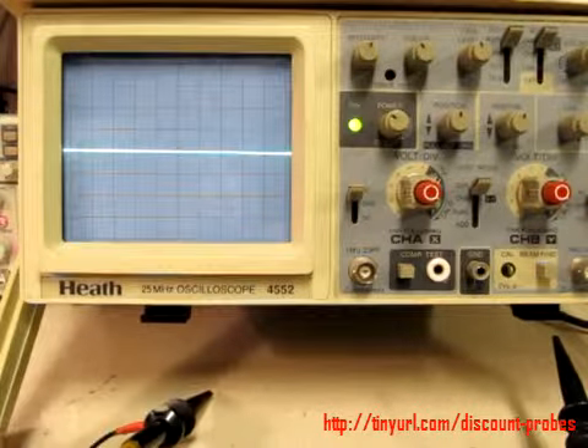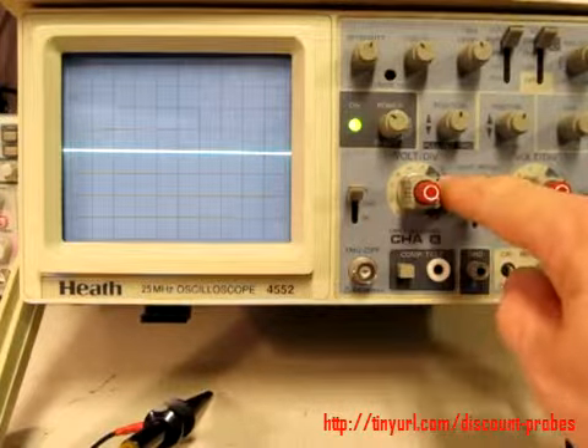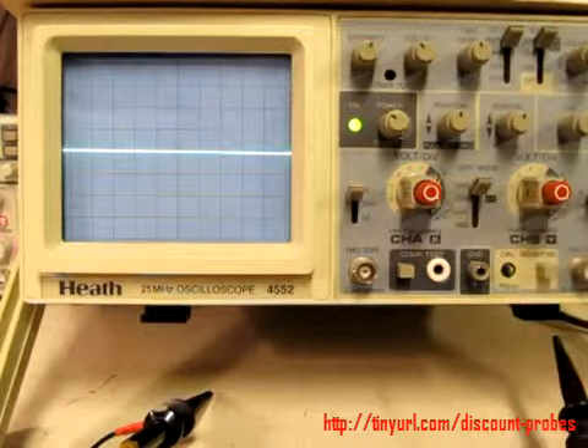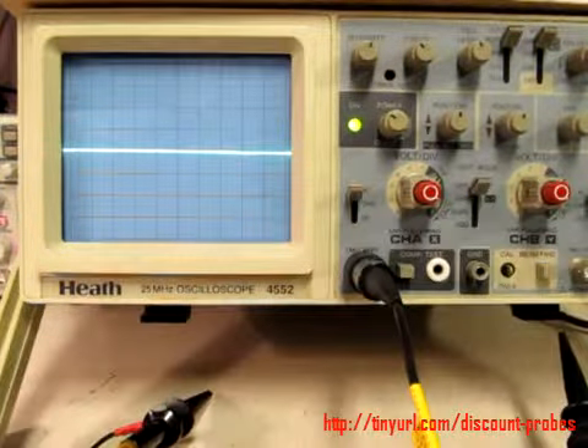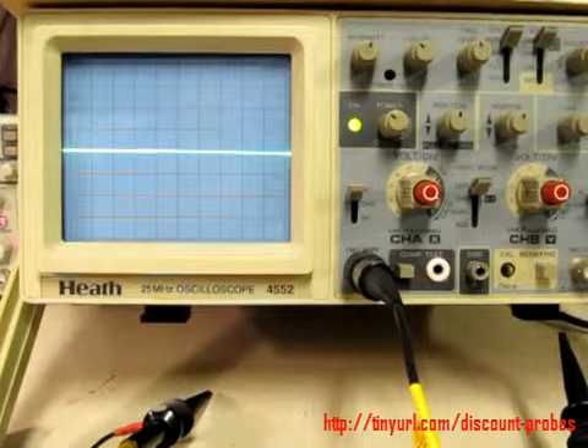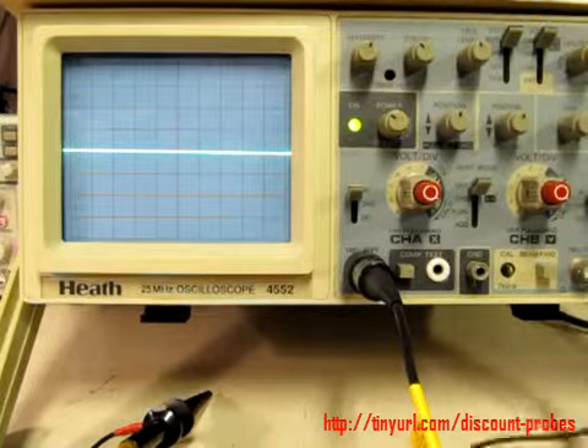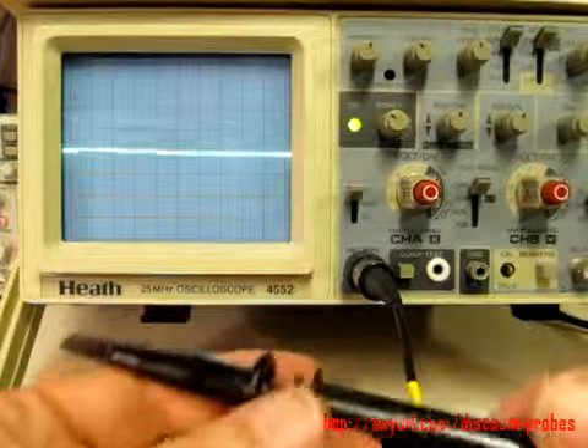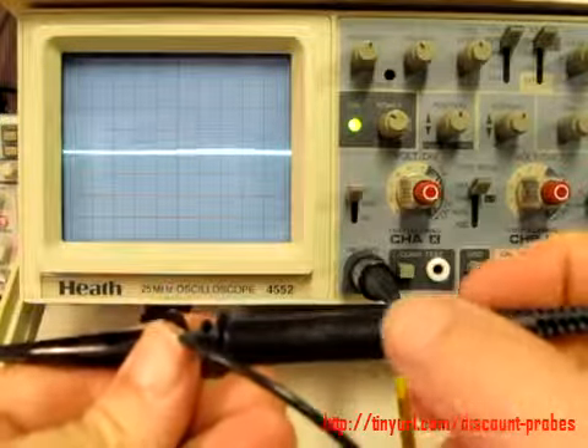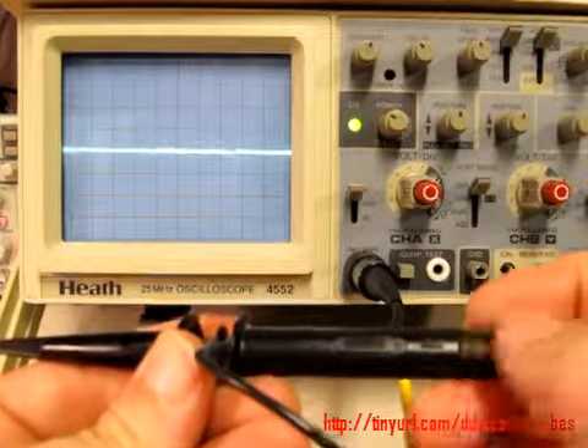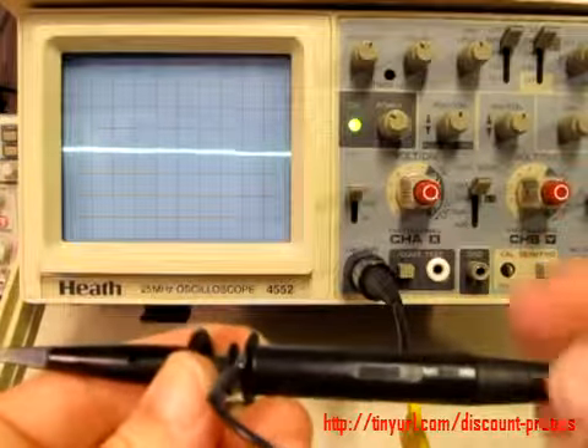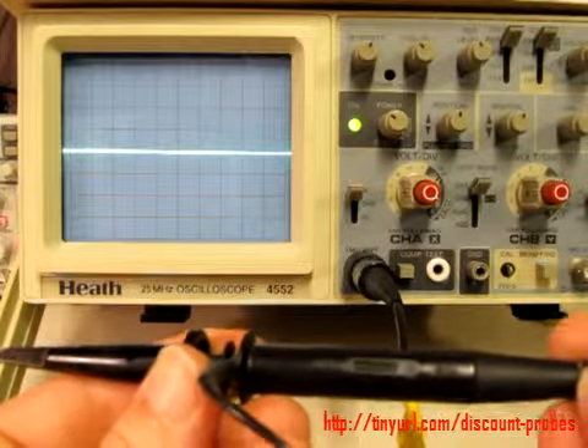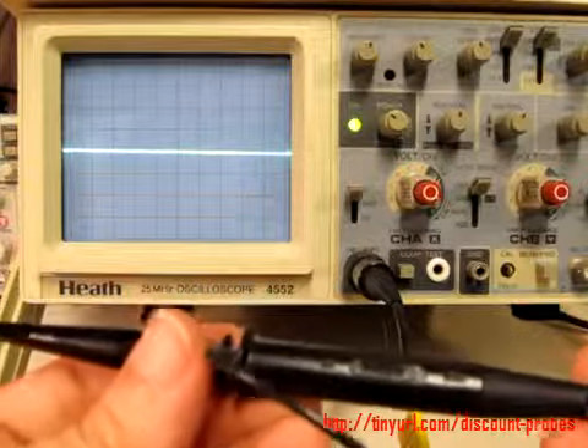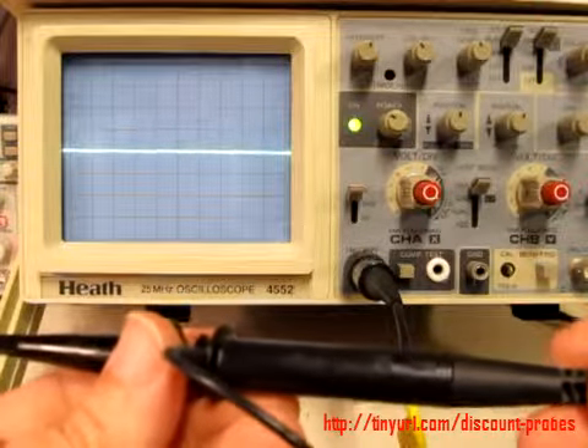So even if the scope channel says 50 millivolts per division like it does here, when I connect up a 10x probe, that is now 500 millivolts per division. Okay, it doesn't tell you that, but you've got to think about that. This probe actually has a switch on it to go from 1x mode, which is just basically a cable connection or coaxial connection right to the probe tip. That's going to have 100 picofarad capacitance or more, but it doesn't have the attenuation.